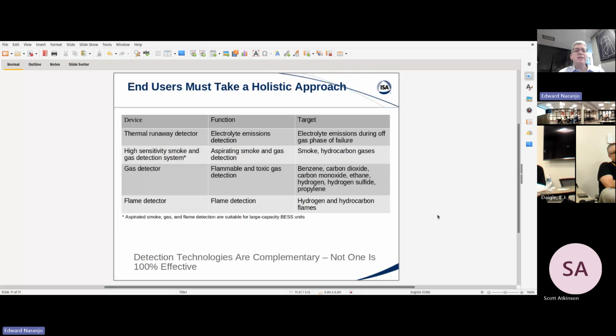Have multiple independent barriers. So in this instance, you can use a thermal runaway detector, which in fact is a preventive method because it detects a failure of a cell before that cell burns. You could also use high sensitivity smoke and gas detection systems, and this is typically used in large capacity BESS units. If it's a small unit, it's unlikely that you will need an aspirated smoke and gas detection system. Gas detectors, both for flammable and toxic gases, are also needed.